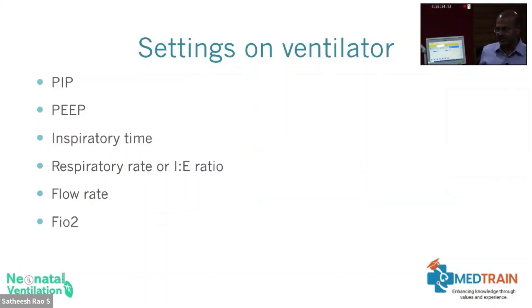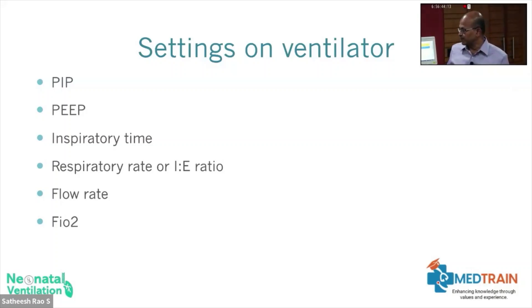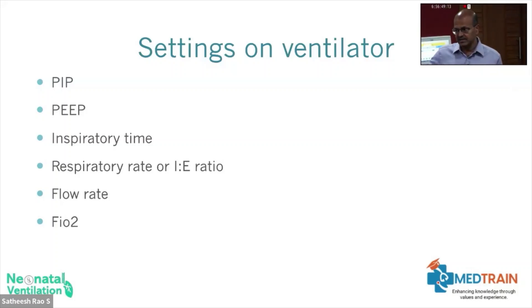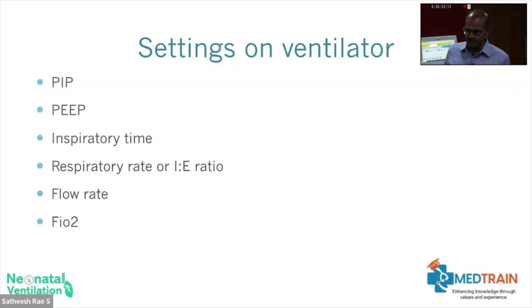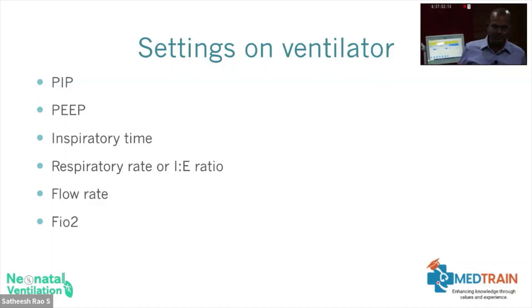All of you are familiar with these settings, but we will quickly discuss each one: peak inspiratory pressure (PIP), positive end-expiratory pressure (PEEP), inspiratory time, respiratory rate, IE ratio, flow rate, and FiO2. The flow rate is most of the time preset by the ventilator and you can adjust the slope. You adjust it only if you want to change the rate of rise — in PSV also you have that rate-of-rise setting.